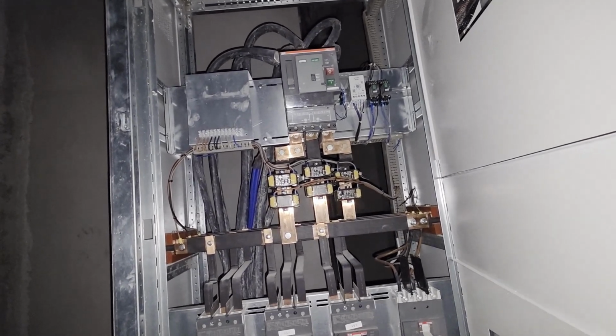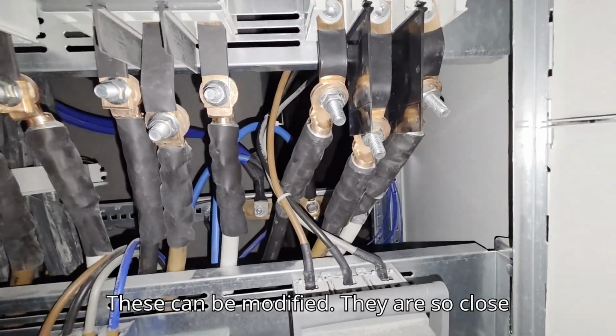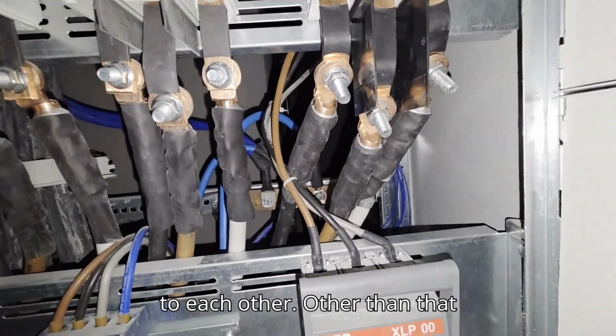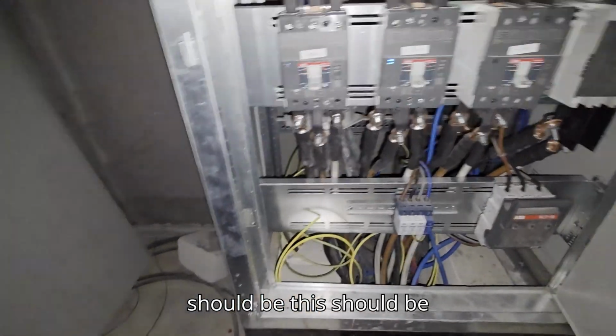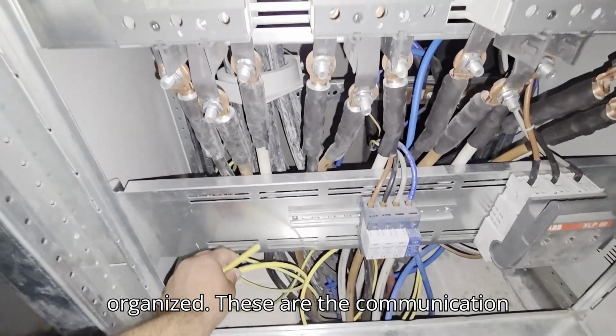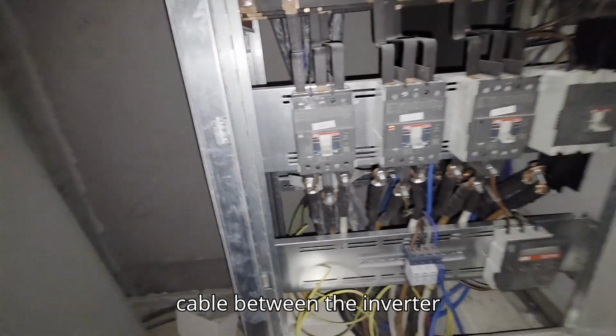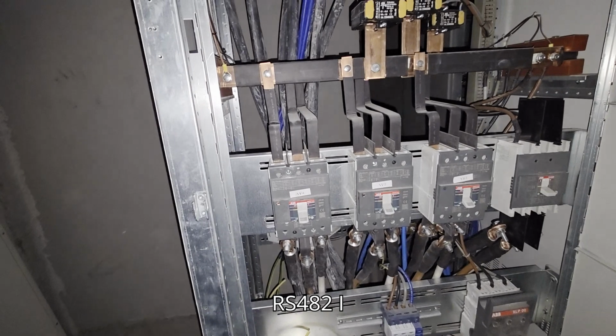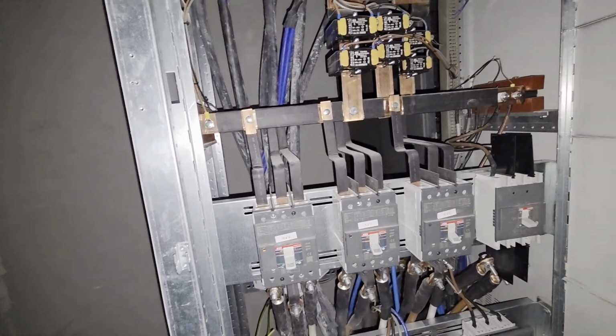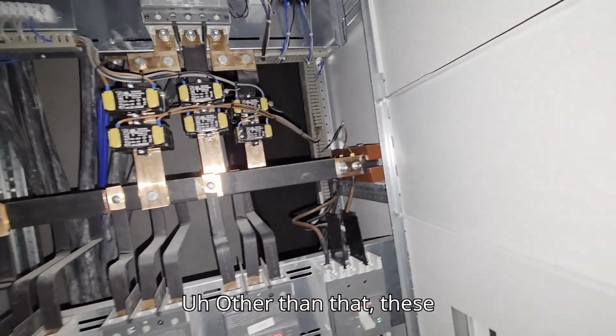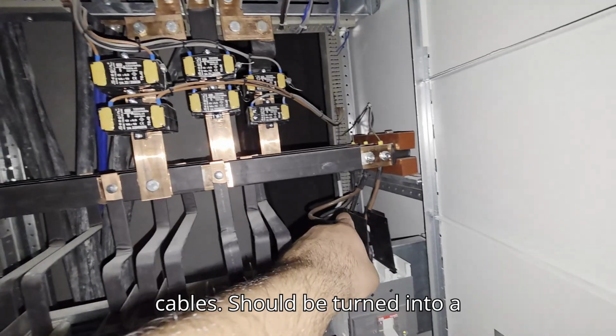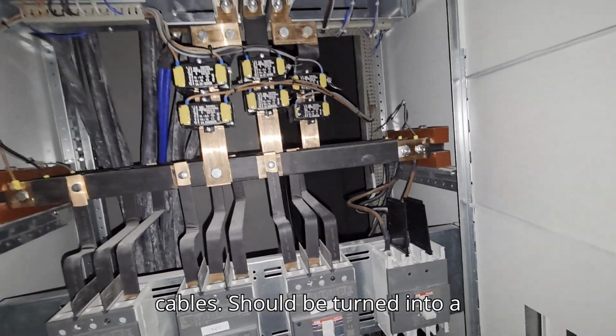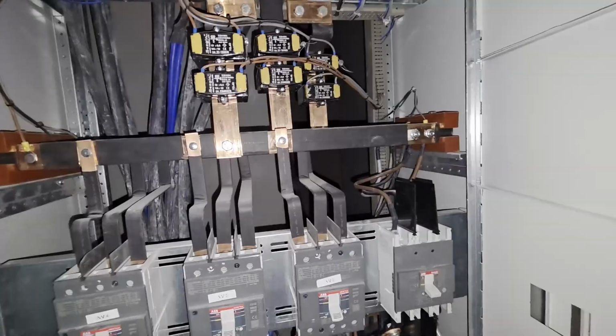Other than that, these can be modified. They are so close to each other. Other than that, this should be organized. These are the communication cable between the inverter, RS485, I think. Other than that, these cables should be turned into a bus bar. That's it.